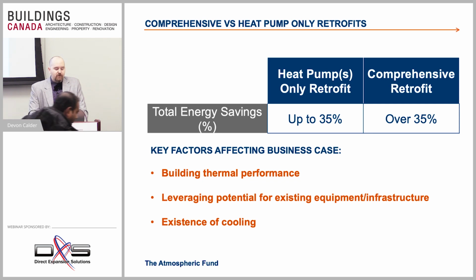Other things that can help with your business case are leveraging existing equipment in the building. So for instance, if you have a building that has electric baseboard heating, but you have a hydronic fan coil that's providing your building with cooling, you could leverage that hydronic loop and tap into an air-to-water source heat pump or a ground-to-water source heat pump.